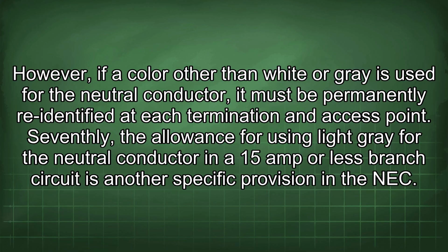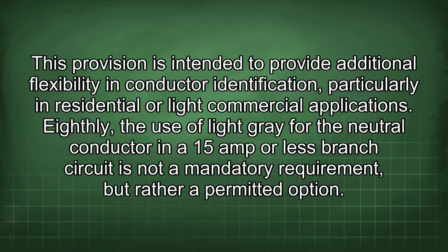Seventhly, the allowance for using light gray for the neutral conductor in a 15 amp or less branch circuit is another specific provision in the NEC. This provision is intended to provide additional flexibility in conductor identification, particularly in residential or light commercial applications.